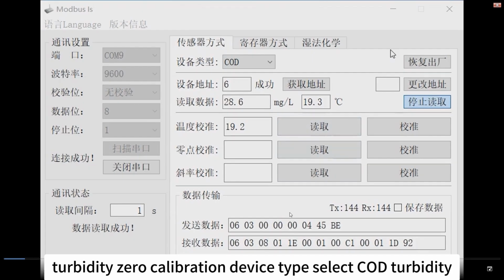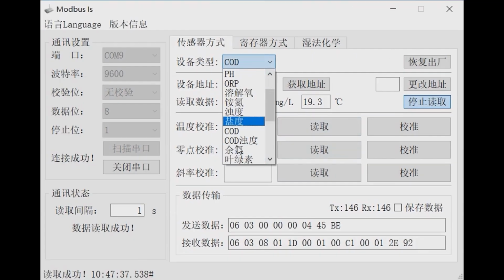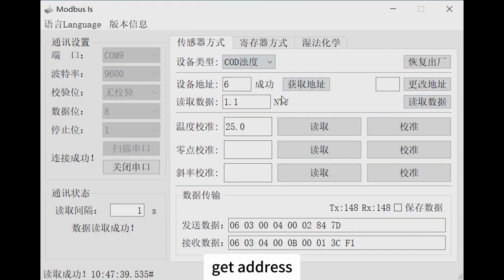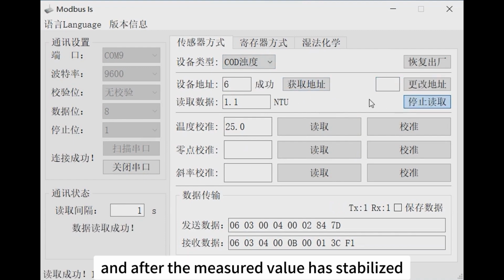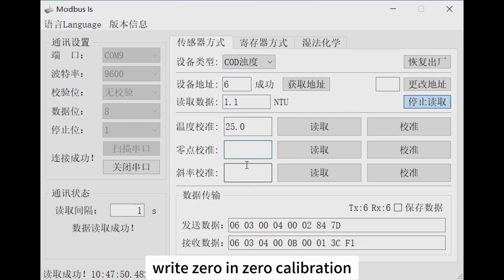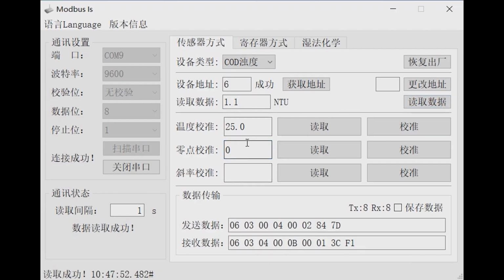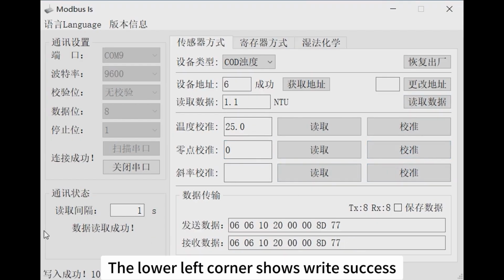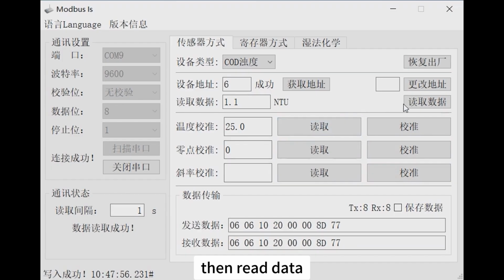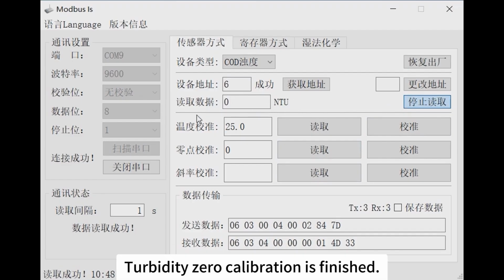Turbidity 0 calibration: device type, select COD turbidity, get address. Read the data, and after the measured value has stabilized, write 0 in 0 calibration. Click Calibration. The lower left corner shows write success, then read data. Turbidity 0 calibration is finished.